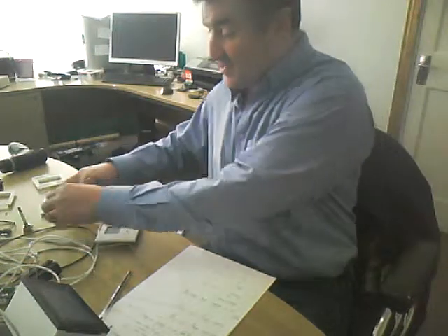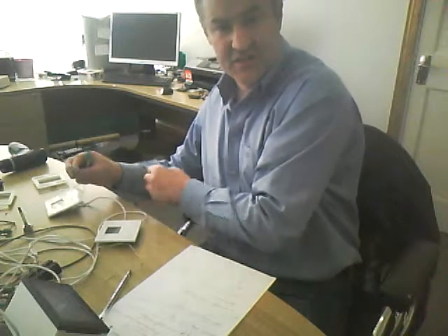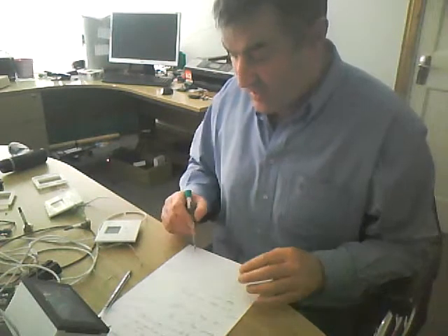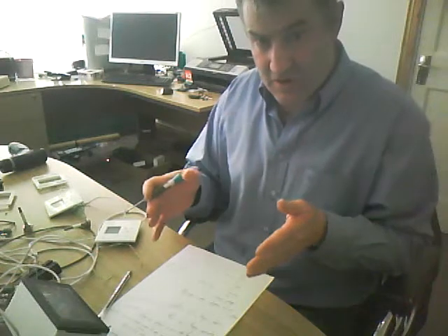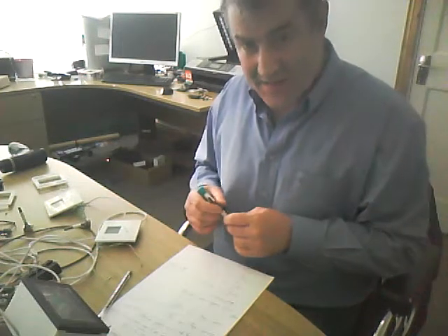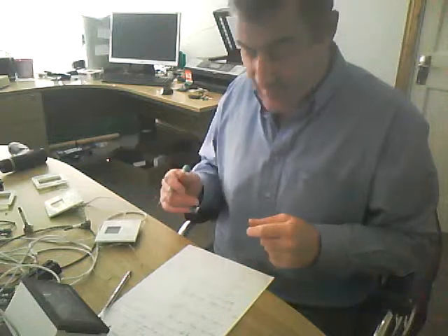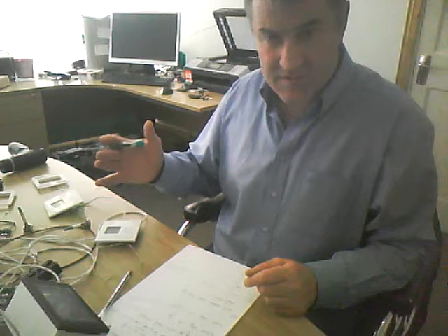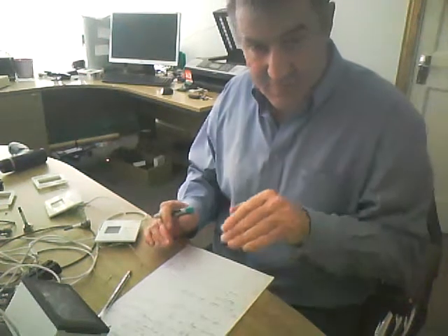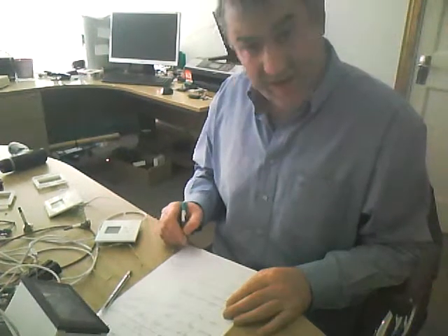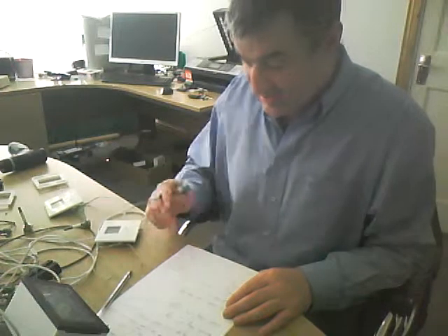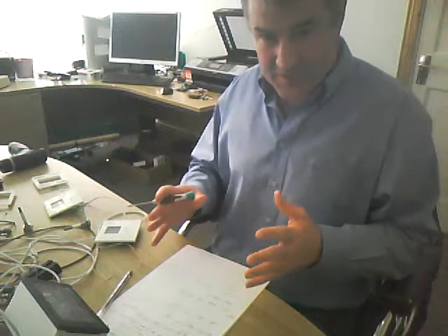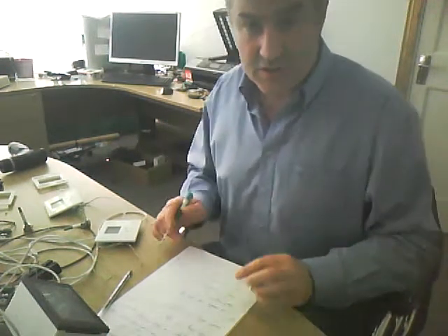I have already used my 2 potentiometers, these guys here, going into channel 2 in each case, to verify that once I went above the temperature of the domestic hot water plus 10 degrees, it turned on, 10 being my max. And it stayed on until as it was dropping down now in temperature, it came to within 5 degrees. That was my minimum, at which point it turned off. And that was verified using the potentiometers and my screen here. So the actual system is working fine. It's a bear to set up, yes, but it does work fine, so it is a pass.